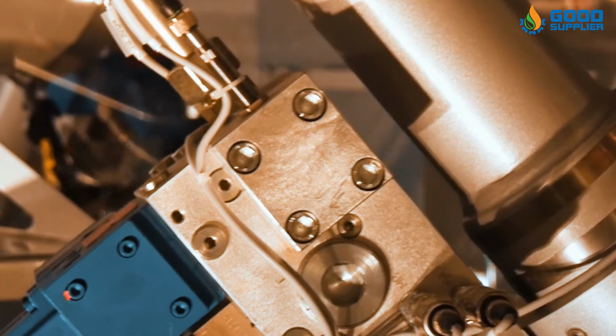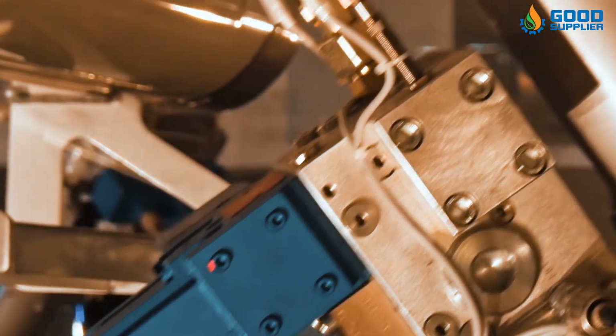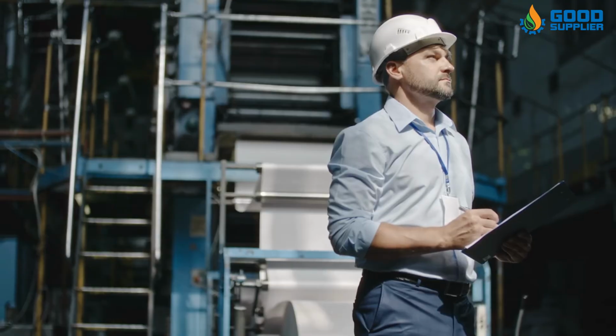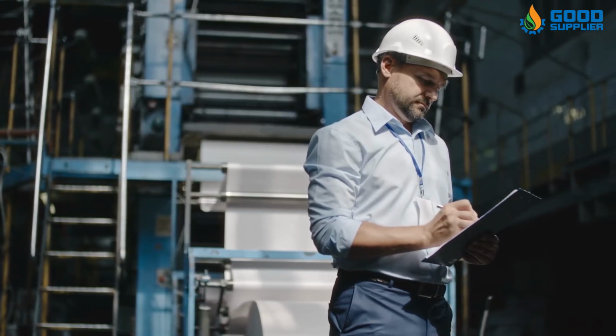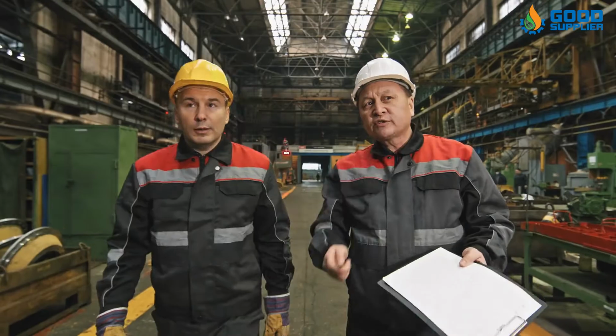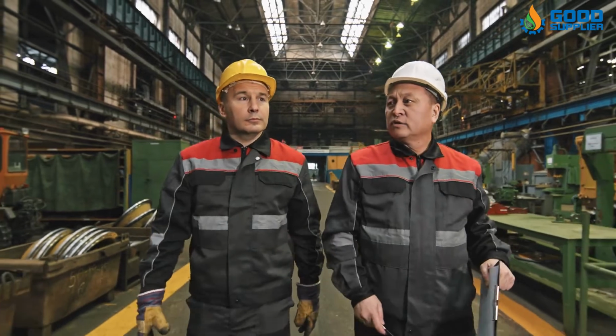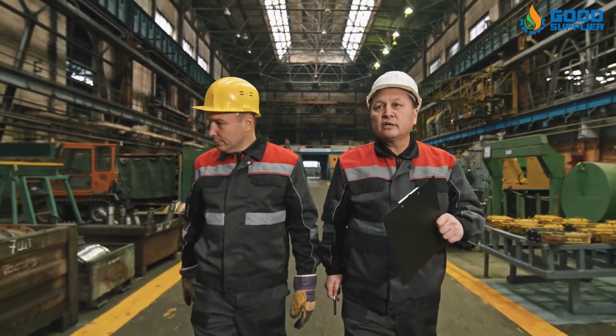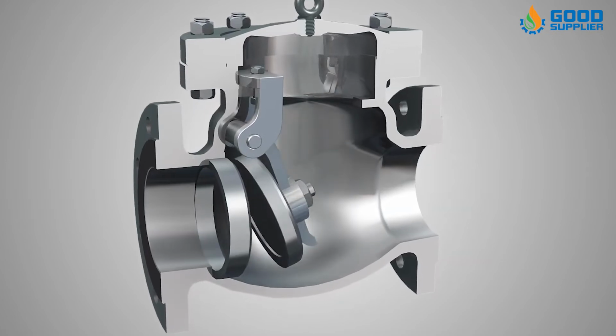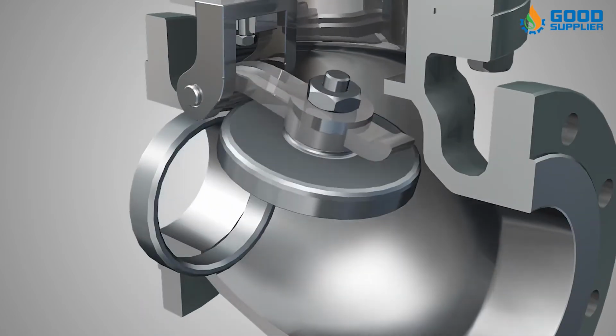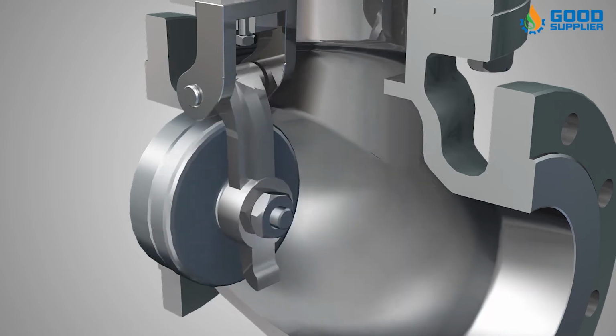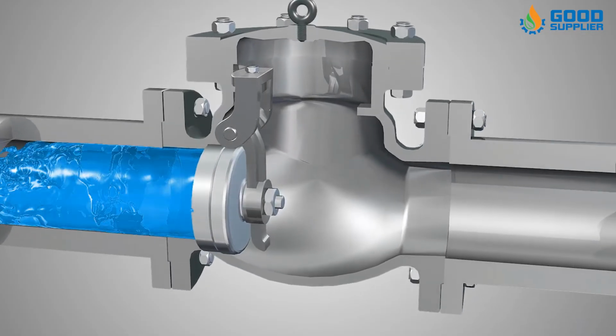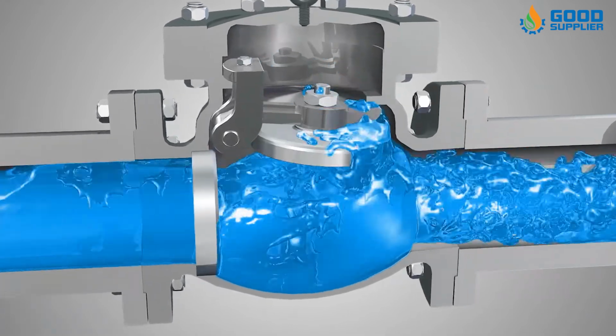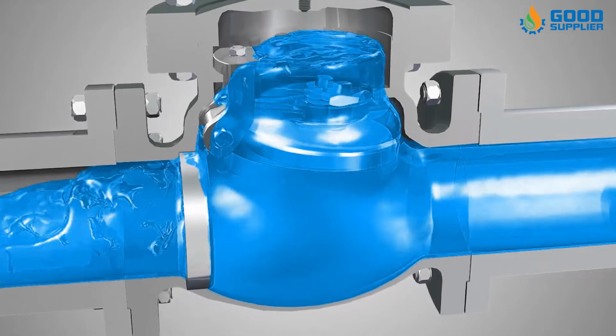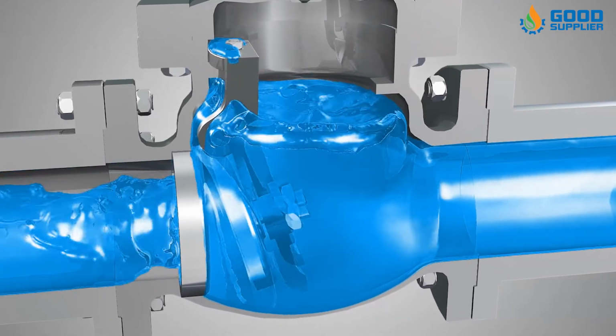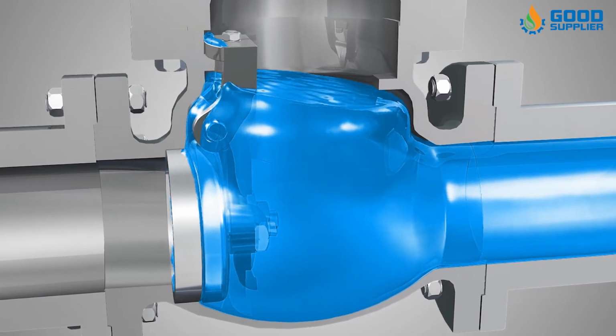There are various types of check valves available for water and wastewater applications. They work in different ways, but serve the same purpose. The most common types of check valves for water and wastewater are swing check valves and ball check valves. A swing check valve is mounted with a disc that swings on a hinge or shaft. The disc swings off the seat to allow forward flow, and when the flow is stopped, the disc swings back onto the seat to block reverse flow. The weight of the disc and the return flow impact the shutoff characteristics of the valve.